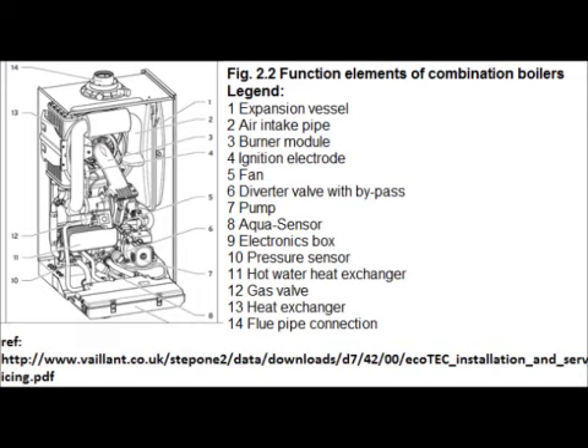The pressure sensor, basically, is all that does. It senses the pressure in the boiler. Should the boiler drop below 1.5 bar, in this case, I believe, off the top of my head, I'm not quite too sure, but I think it's about 0.7 bar. If it drops below this pressure, then the boiler simply drops to a fail-safe and cuts out. Because if it doesn't have any water inside the system, you'll damage the system. You'll damage the boiler. The boiler can't run without water. It needs water to run. It's as simple as that.